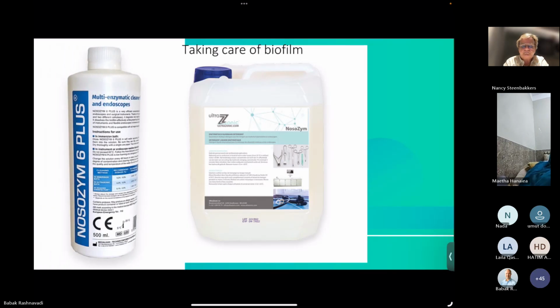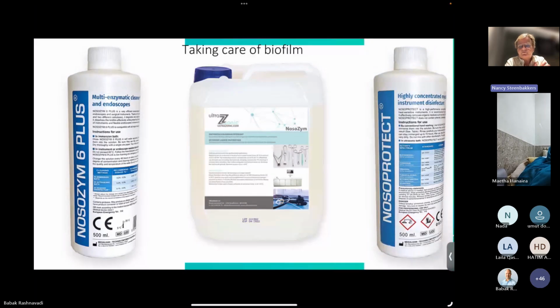Next, please. Oh yeah, then of course, if the biofilm is really there, then you have the Nosozyme 6+. And this Nosozyme 6+ is with 7 enzymes. You can kill the biofilm when it's really very tough biofilm and you cannot succeed anymore with your original detergent. Then you can use this detergent, and you can put it in a tray with water, and you respect about 10 or 15 minutes, and your biofilm, which is really sticky on your endoscope, will be gone. So this is also very helpful for you. Next, please.